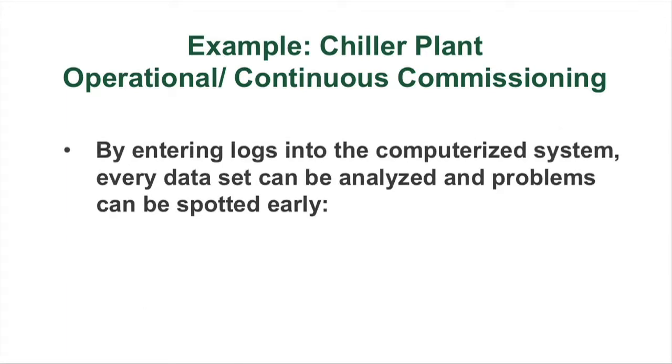By taking those logs that are already being collected and entering them into a computerized system, every data point can be analyzed and problems can be spotted early. The point here is that you don't have to have a utility monitoring system that actually meters all these points. If you're already collecting this information, you can simply plug it into the system and then run diagnostics on that data in your utility monitoring system.